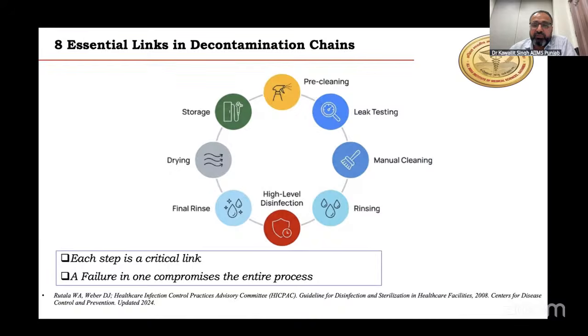This is further followed by manual cleaning, followed by rinsing with the enzymatic solutions, which is followed by the high-level disinfection, exposure to the high-level disinfectant for an adequate period of time under adequate temperature that is given by the manufacturer, which is then followed by the final rinse with the sterile water, ultimately followed by drying, and ultimately storing them in a vertical manner in specialized slabs that are available.